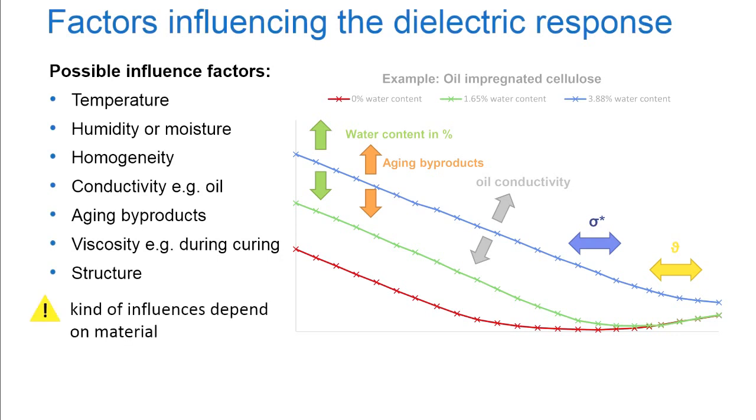Attention! Dielectric parameters are also influenced by the material itself and the sample dimension. Thus we recommend to use the capacitance ratio of two frequency points, for example at 10 millihertz and 50 hertz.